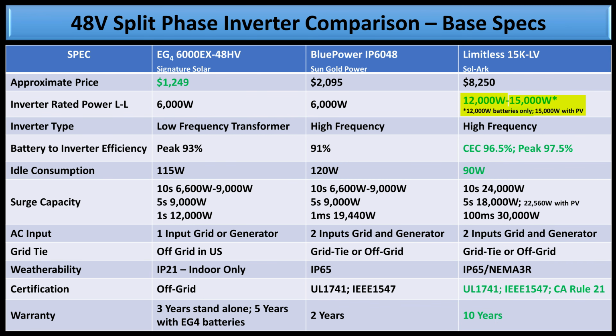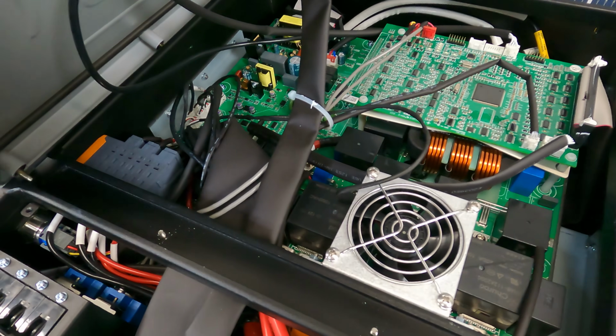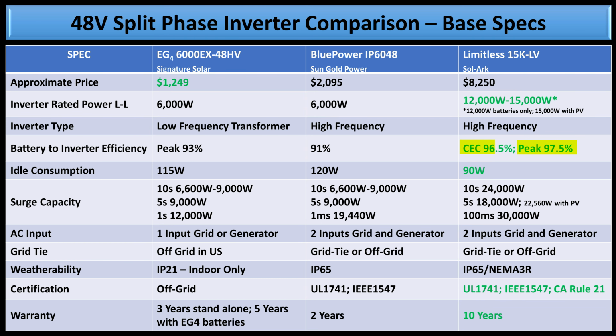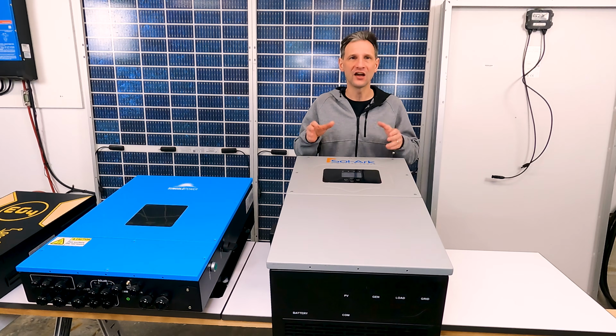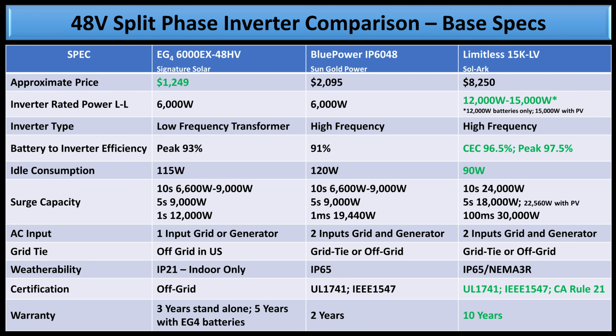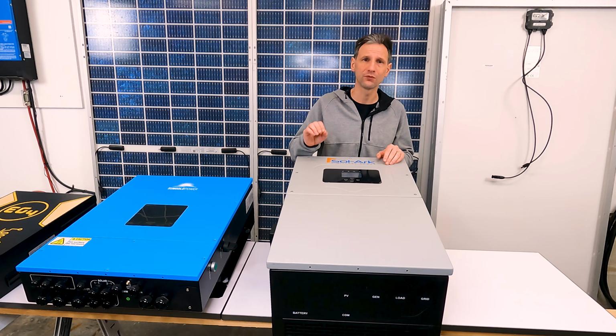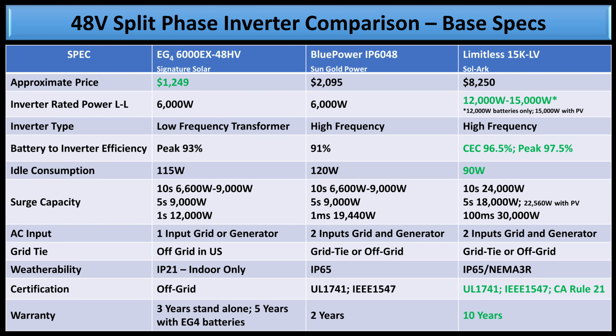It's a high-frequency inverter with a whopping peak efficiency of 97.5%. Even its average efficiency is 96.5%. And the idle consumption is the lowest of the three at 90 watts. Its surge load capacity is double its rated capacity at 24,000 watts for 10 seconds and 18,000 watts for 5 seconds. It can take a peak of 30,000 watts for 100 milliseconds.